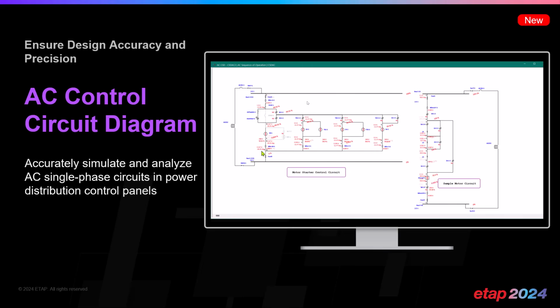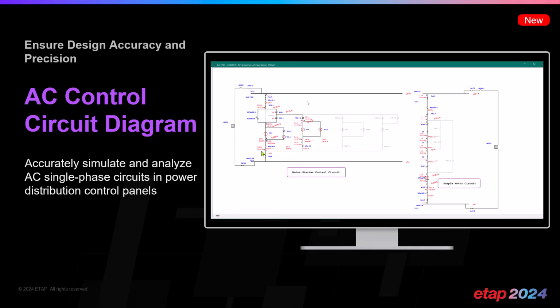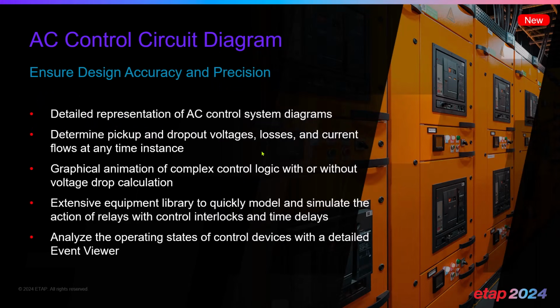will work adequately. Of course, most systems are designed with these control circuits to be operated nominally, but AC control circuit diagram is particularly beneficial if you want to also analyze cases where you're not only designing the system, but you also want to make sure that the system operates correctly under degraded voltage conditions, or in cases where your operating voltage is off nominal and you want to make sure that your safety and shutdown systems have adequate voltage and they operate correctly.